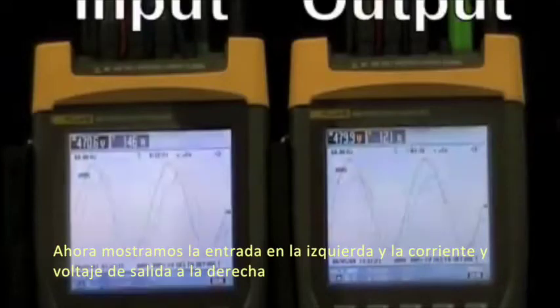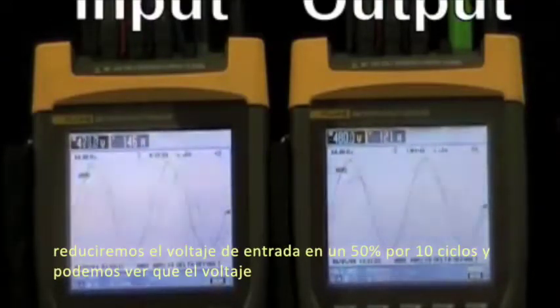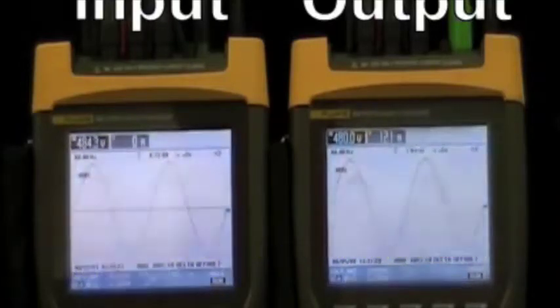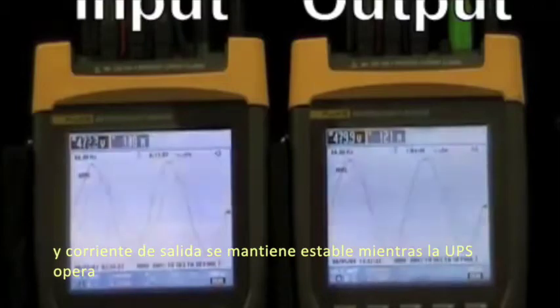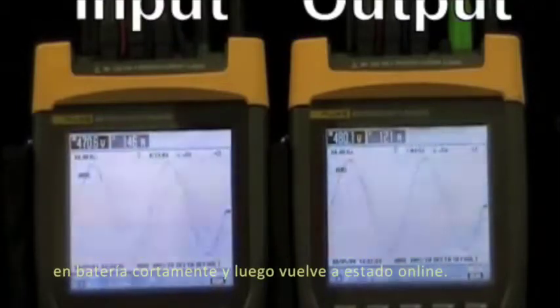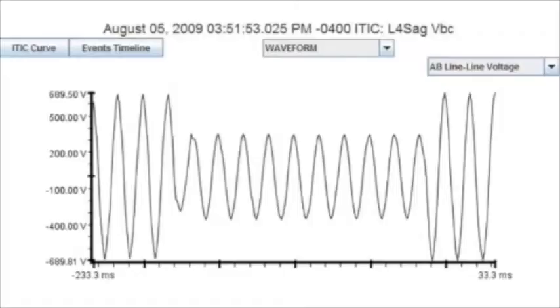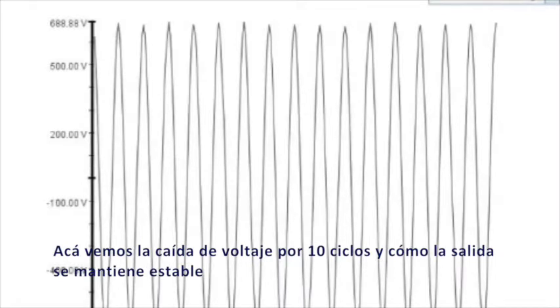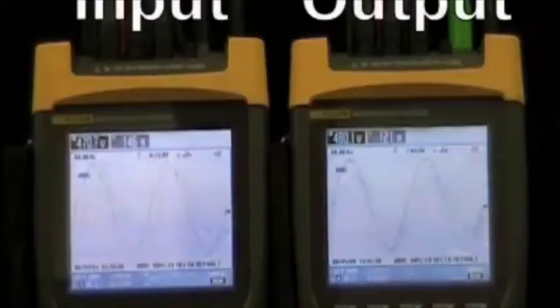Now we show the input on the left, output voltage and current on the right. We will reduce the input voltage by 50% for 10 cycles. And you can see the output voltage and current remain undisturbed as the UPS operates on battery briefly and then goes back online. Here we see the 10 cycle 50% sag and the output of the UPS undisturbed during the sag event.